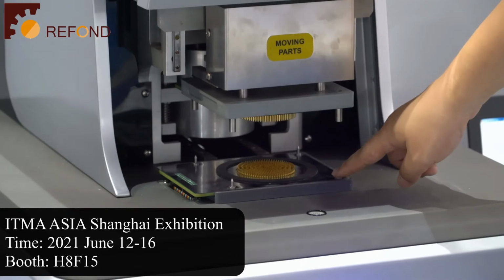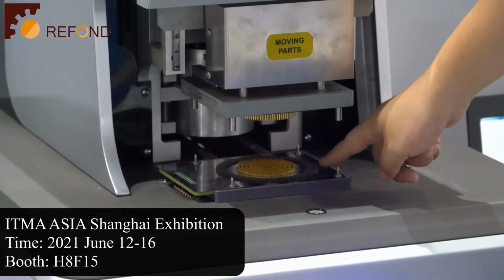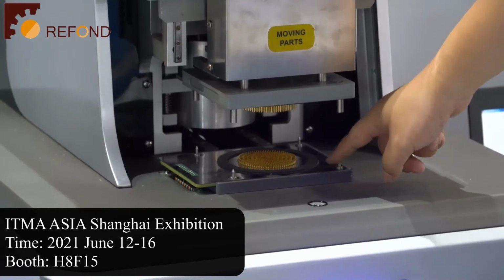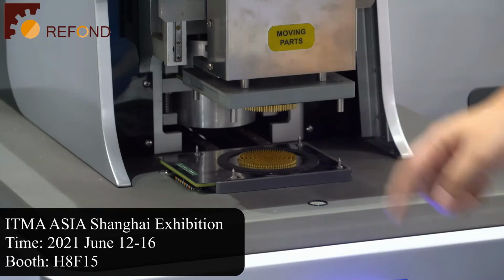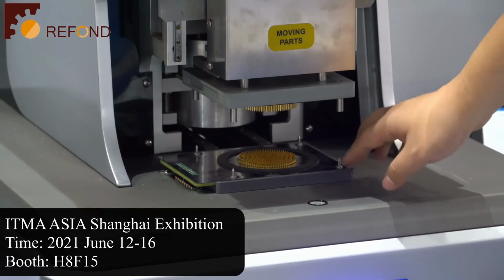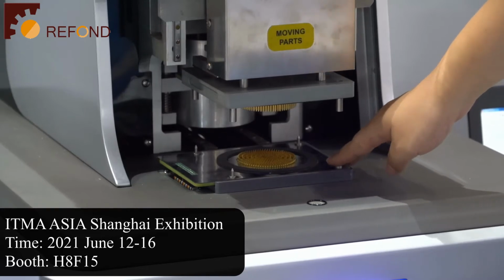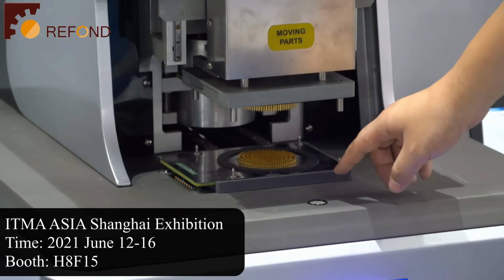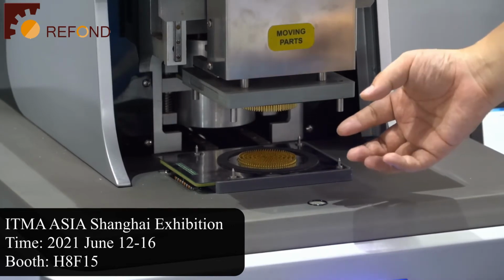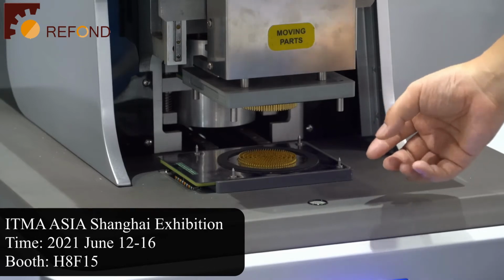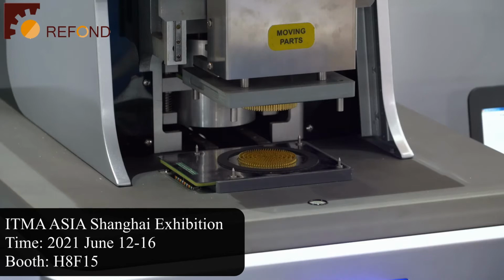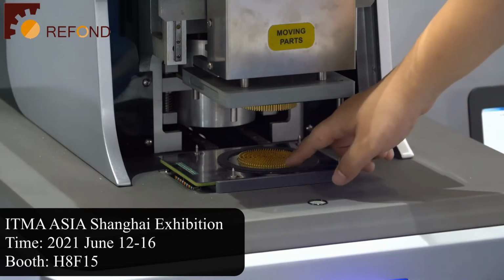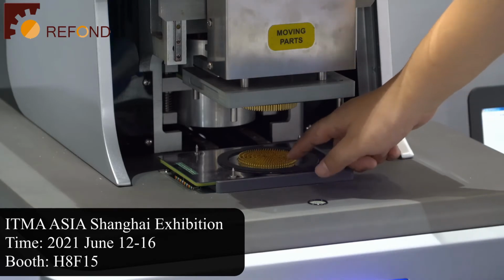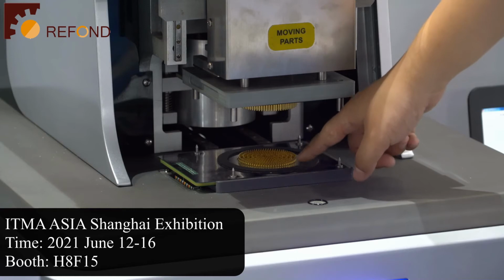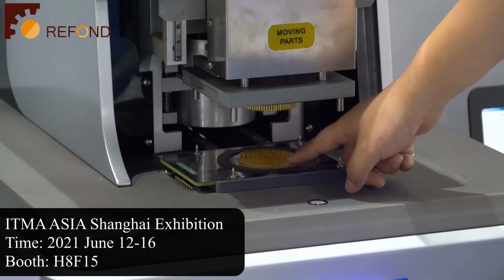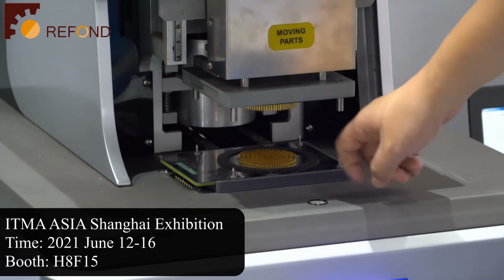In addition to the requirement of the standard, we made a lot of innovation. First of all, the amount of water to be pumped required by the standard is 0.2 milliliters, and we made it adjustable to a range of up to 0.45 milliliter, with still the same precision required by the standard. So you can choose to use a different amount of test liquid for the test other than the one required in the standard. Also, we have more test zones on the test probes than required by the standard, so we can make more detailed and precise measurement of the distribution of the moisture, the water, on the fabric.